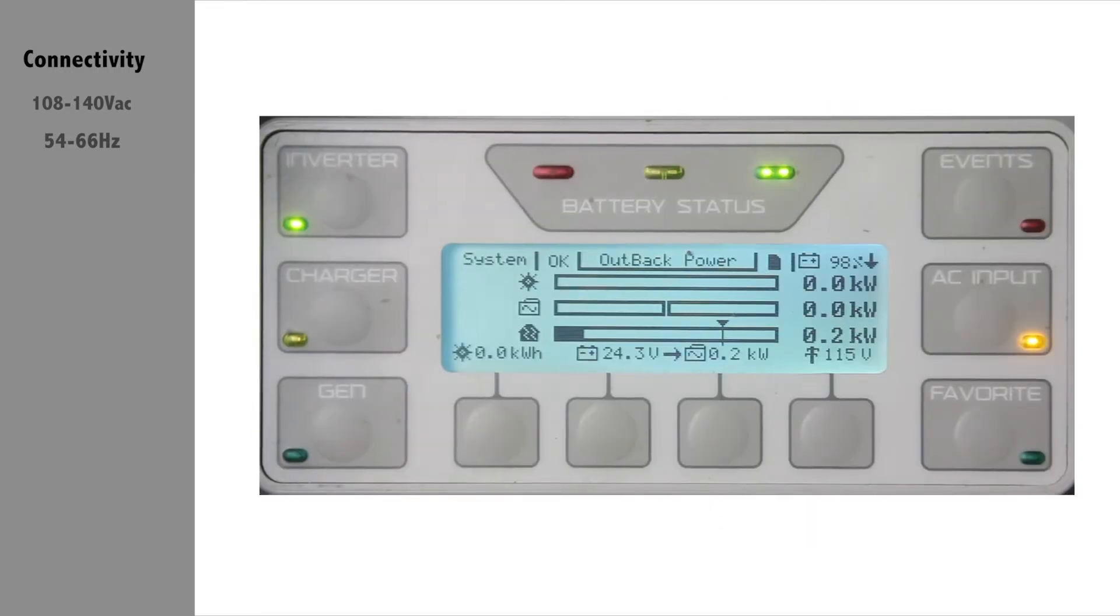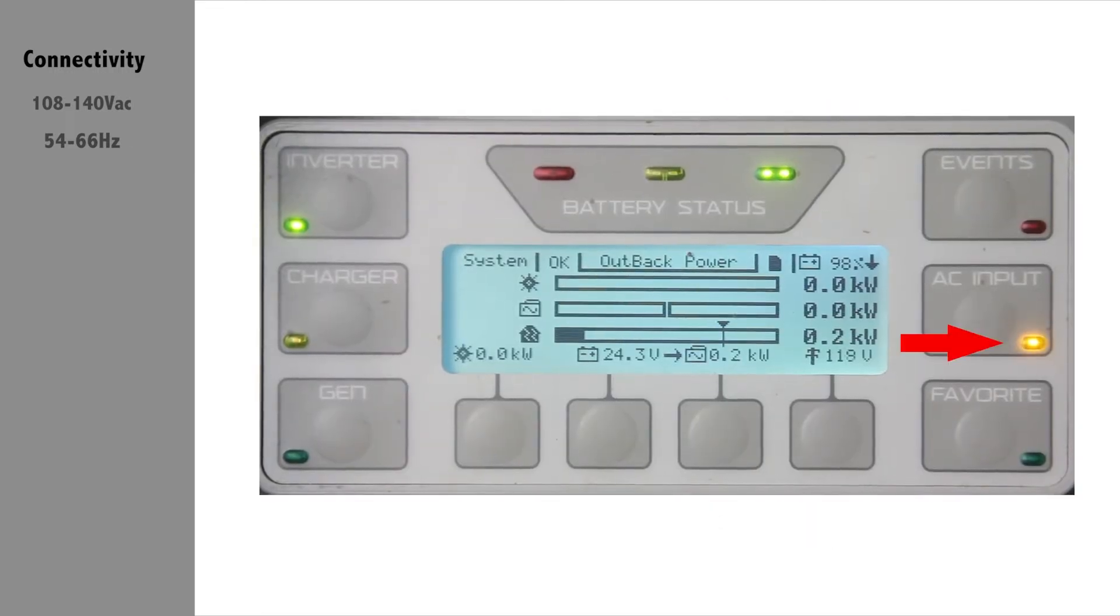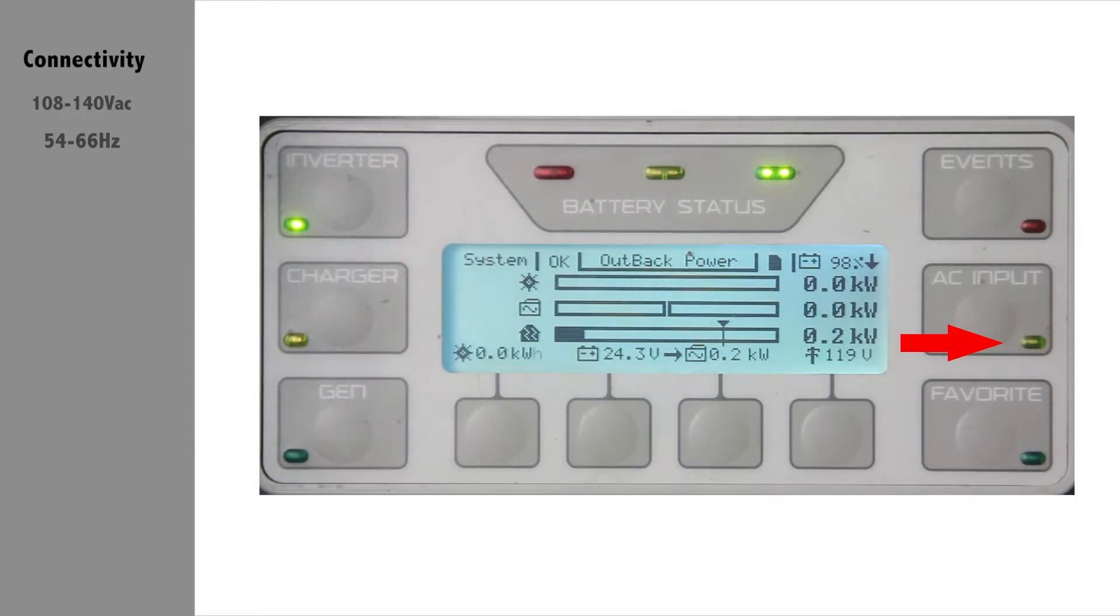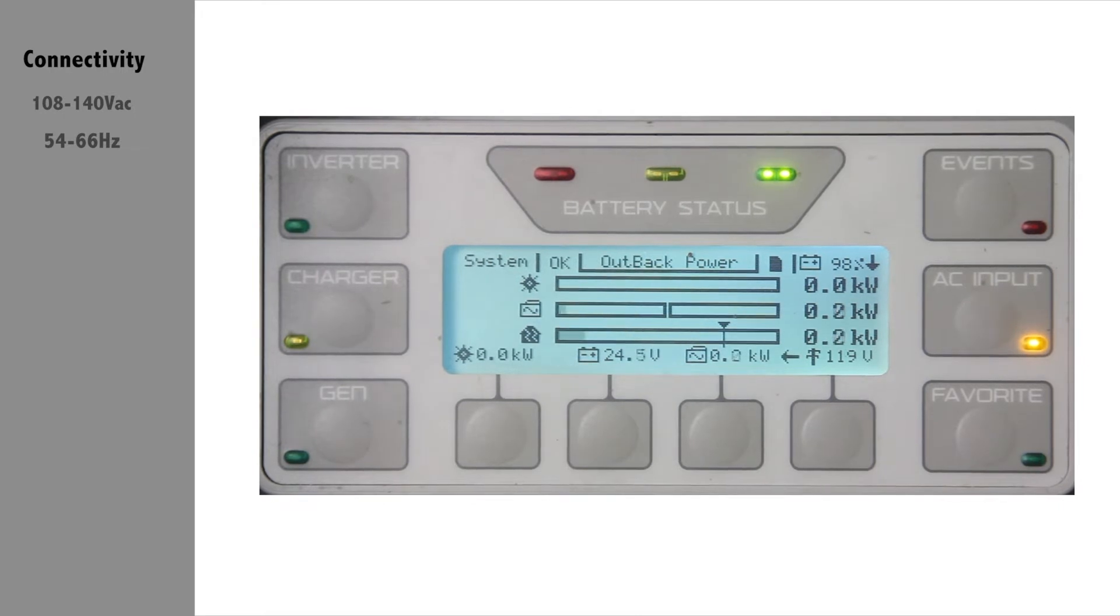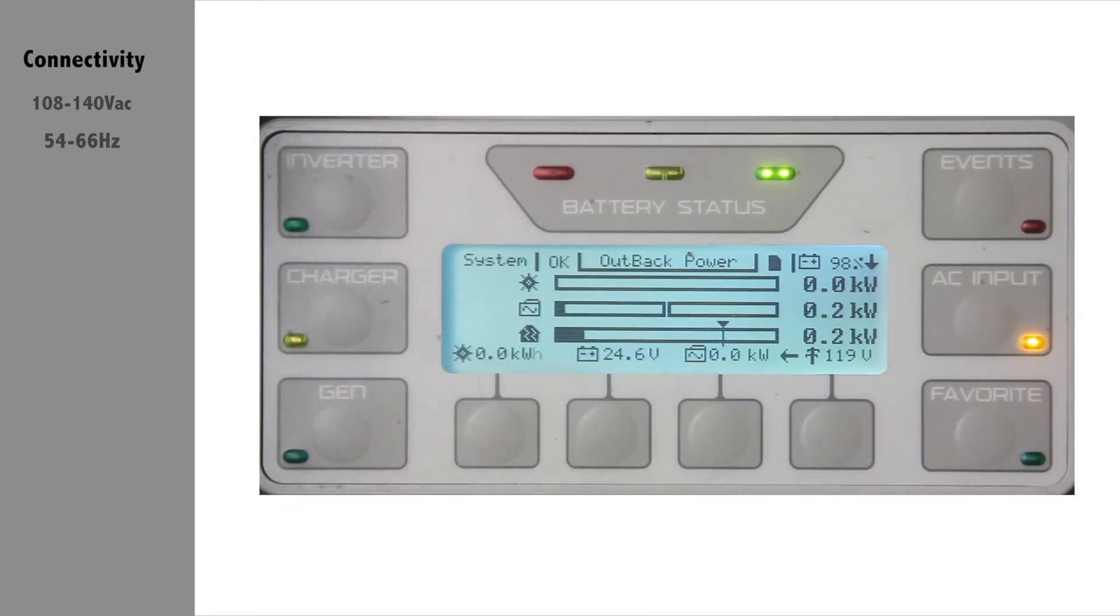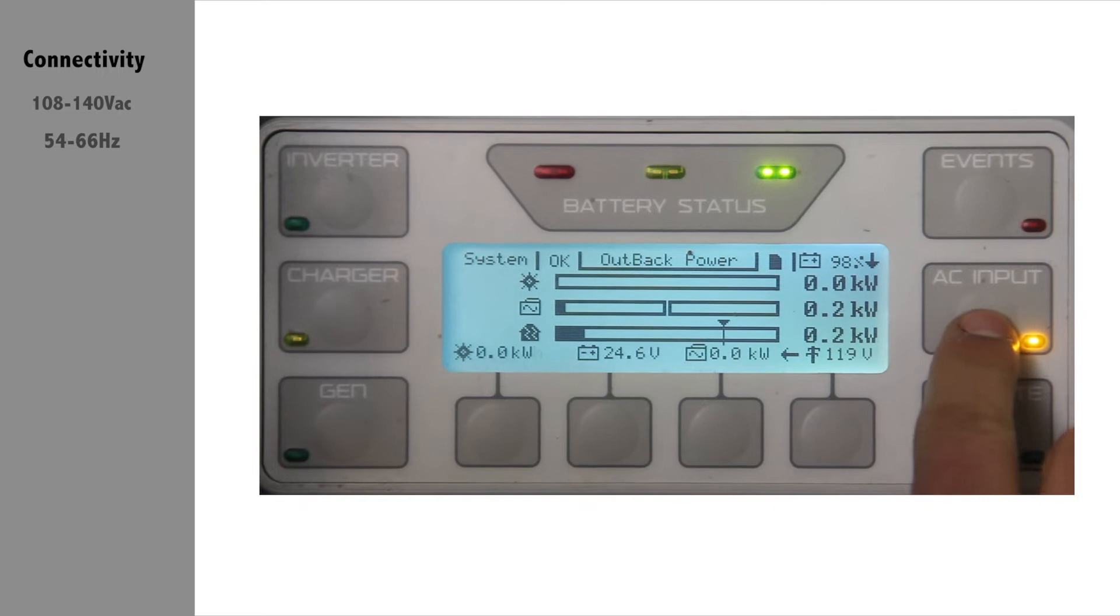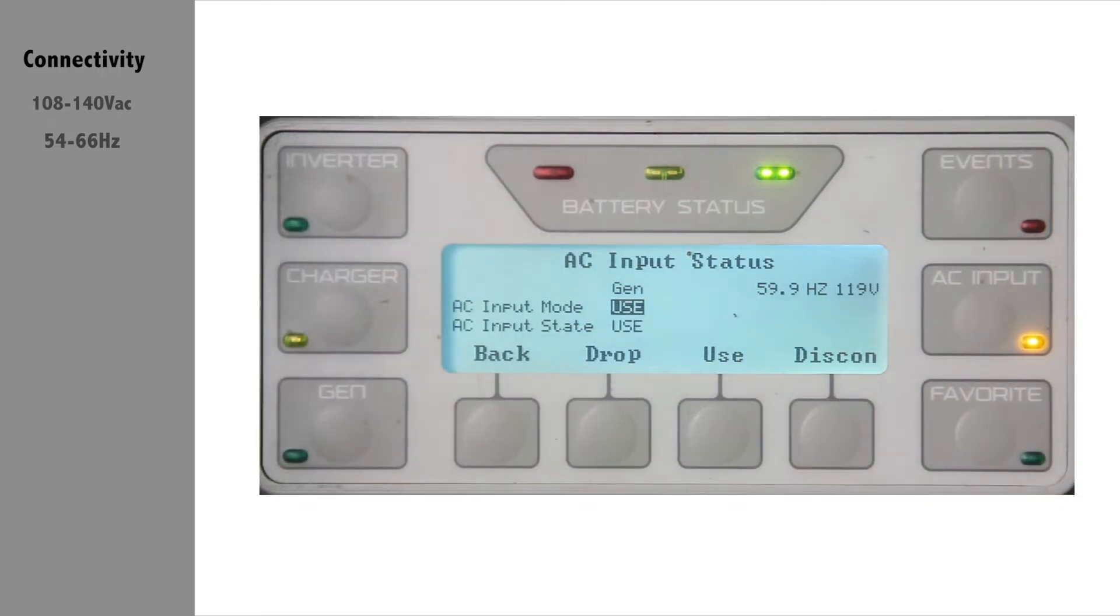The Mate 3 will show when the AC source is present with a blinking AC input light. Once the source is accepted and connected, the amber light will turn solid and simultaneously the green inverter light will turn off. If it doesn't, press the AC input button and make sure your AC input mode is set to use.